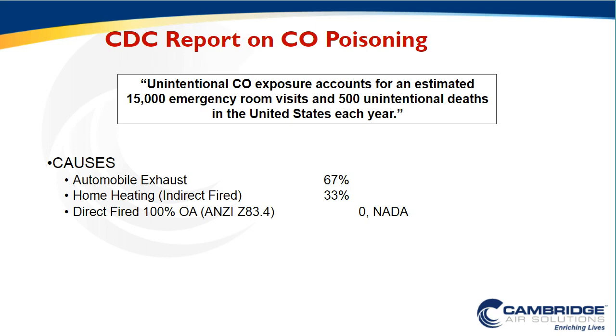So I'll ask the question, why? I'll let you sit there and think, what is it that causes the CO levels inside these spaces to reach unsafe levels? What is the reason that even an indirect fired system, a mechanical system that is designed to separate the product of combustion from the delivered air, was resulting in 1/3 of the CO exposures, yet 0 systems from the direct fired?